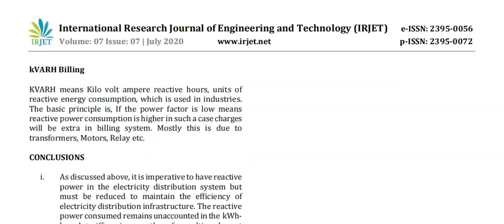kVARh means kilovolt-ampere reactive hour, the unit of reactive energy consumption, which is used in industry. The basic principle is that if the power factor is low, reactive power consumption is high, and in such a case charges will be extra. This is mostly due to transformers, motors, relays, etc. In conclusion, it is imperative to have reactive power in the electricity distribution system, but it must be reduced to maintain the efficiency of the distribution infrastructure. The power consumed remains unaccounted in the kilowatt-based tariff regime if the power factor penalty does not adequately compensate the utility for the unaccounted reactive energy.